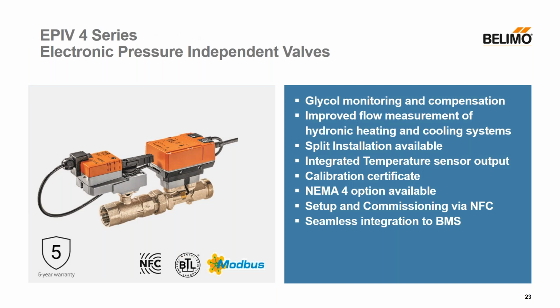Coming later this year in the third quarter, we have the EPIV version 4, which complements the EV4 for pressure independent applications and shares many of its design improvements, including improved flow measurement for hydronic heating and cooling systems, split installation available to allow the flow meter installation separate from the valve body, seamless integration into the BMS with BACnet MSTP or Modbus RTU, integrated temperature sensor output into the flow body, eliminating one remote sensor, glycol monitoring and compensation, digital calibration certificate, and NEMA 4 options are available. Can also set up and commission via NFC and the Belimo Assistant app.